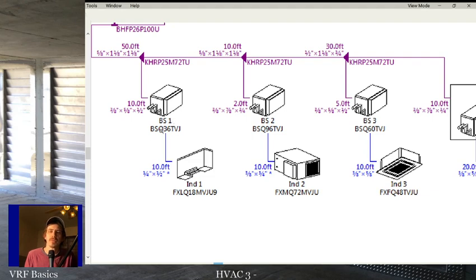Obviously, because you only have 2 lines going to each, and there's no way for you to make those do different things at the same time. But this branch selector, this unit could be in heating, and over here on this branch selector, this unit could be in cooling, and you wouldn't have any problems. If this one's in heating, discharge goes in that unit. It basically turns that unit into a condenser, and liquid comes back from it. And then in this one, if it's in cooling, liquid goes to that unit, suction comes back. That's an evaporator. Right, and you can switch them at will at that branch selector.